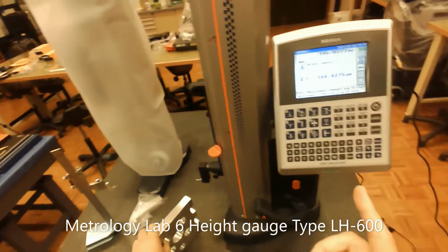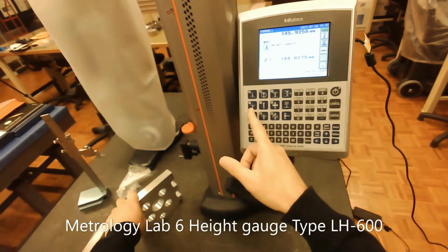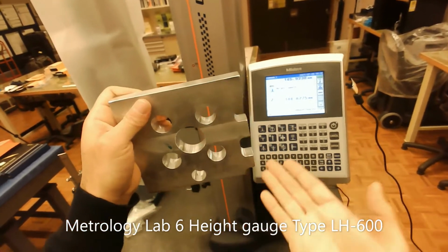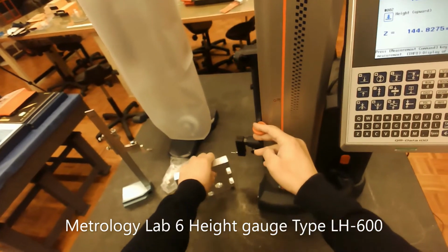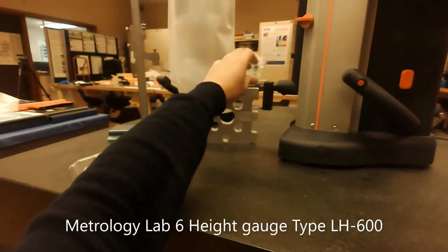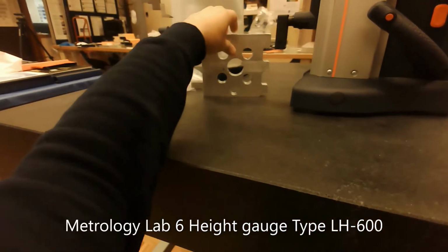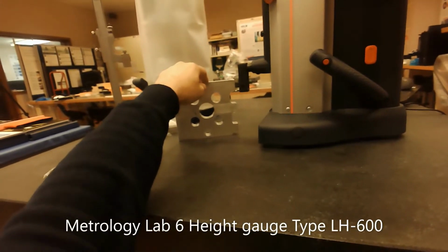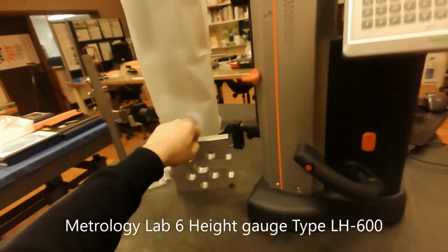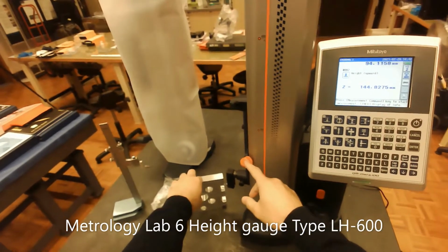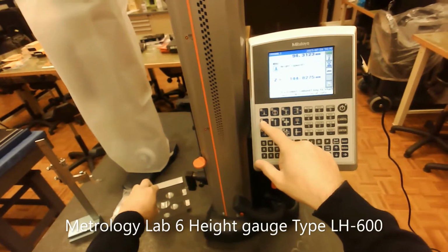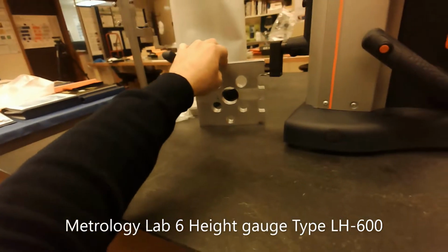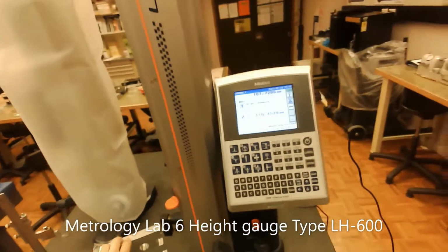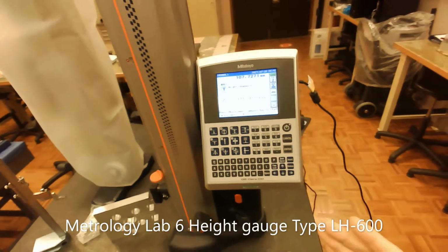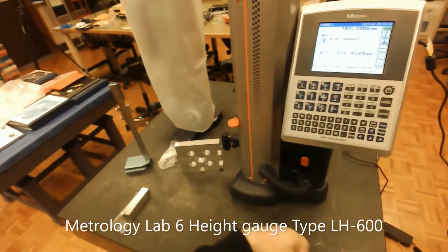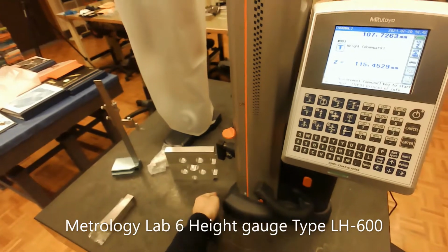Now, the other operation that this device can do is checking the height from the bottom. So I can check the height of this surface from the reference, which is the bottom table. I can put the device in this position, and when it goes up, it's going to touch the surface. Because this part is aluminium, I need to support it by hand when I press the button. So I'm going to push it once again a little bit down, so I have the chance to see how it's going to work. Press that, and it tells you that the thing is going up, touches the table, and gives us a reading of 115.4529. Now that's the height of this surface from the table.